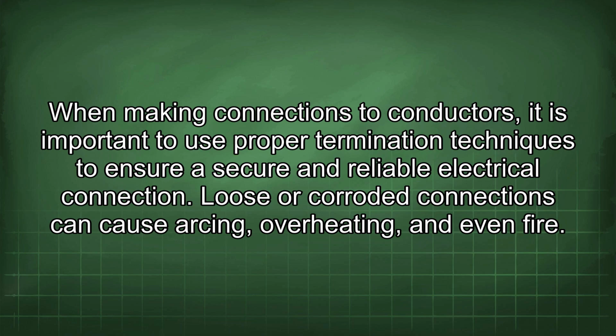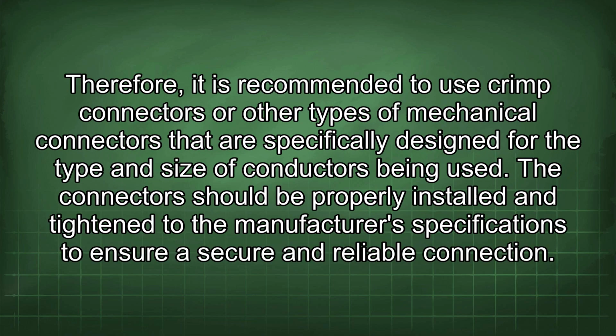When making connections to conductors, it is important to use proper termination techniques to ensure a secure and reliable electrical connection. Loose or corroded connections can cause arcing, overheating, and even fire. Therefore, it is recommended to use crimp connectors or other types of mechanical connectors that are specifically designed for the type and size of conductors being used. The connectors should be properly installed and tightened to the manufacturer's specifications to ensure a secure and reliable connection.